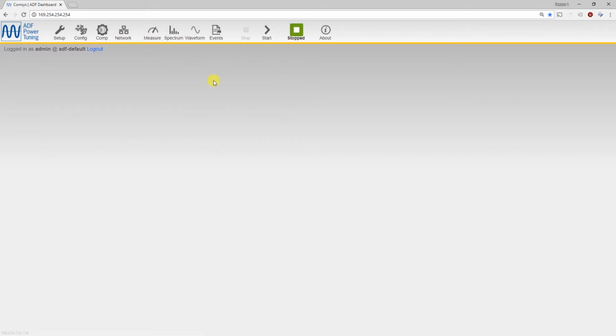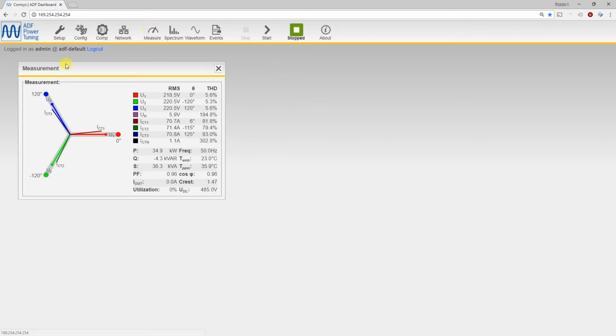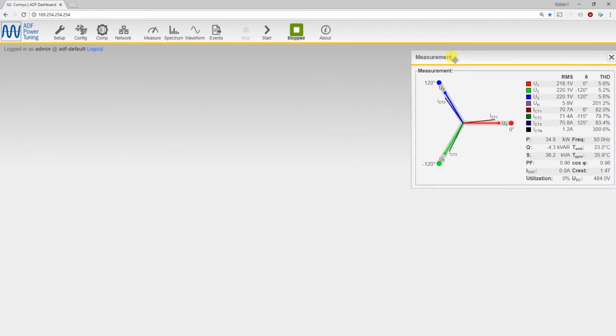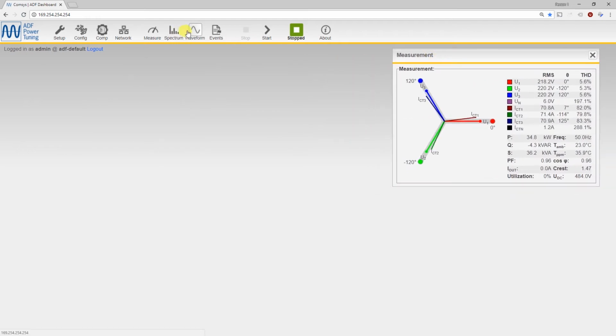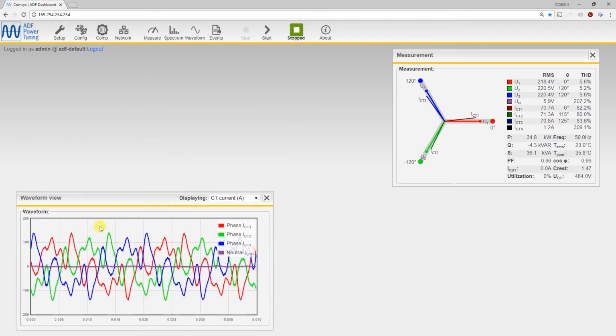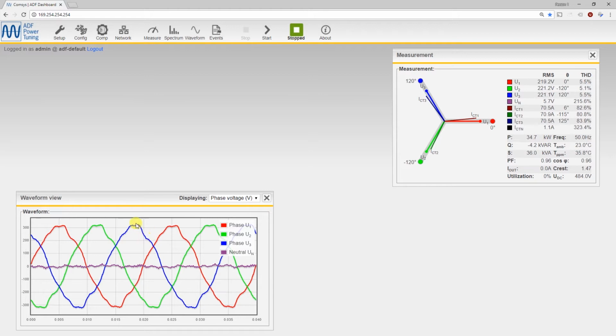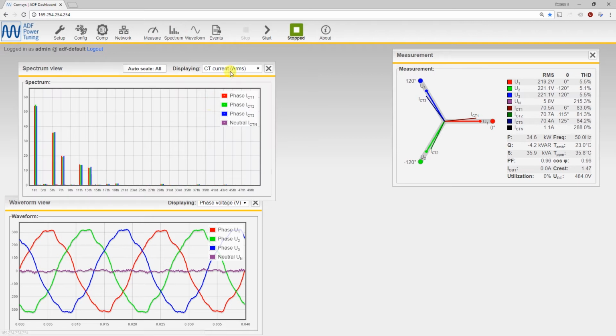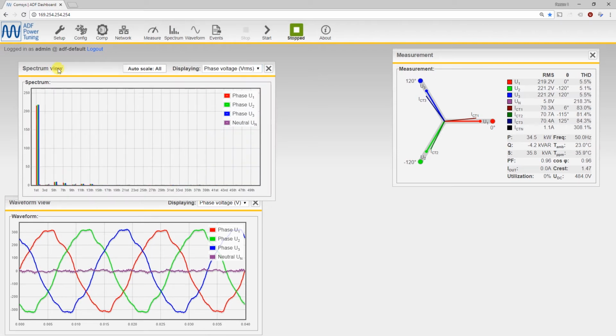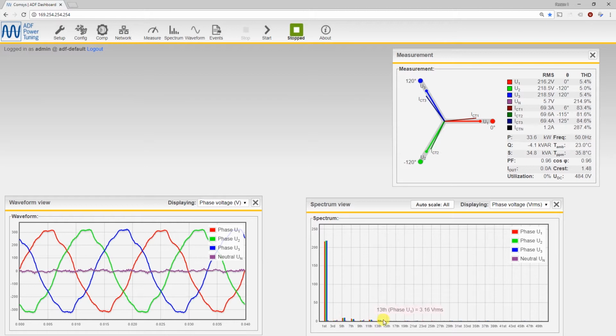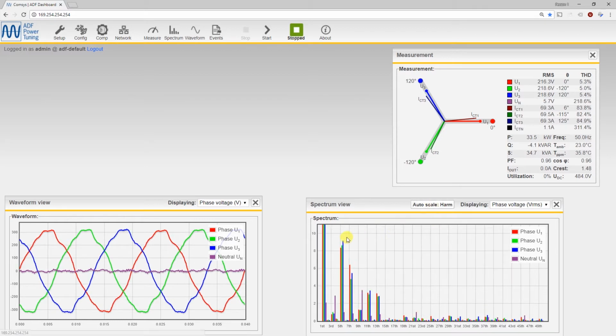To do the sensorless control, we want to open a few windows. An important window always to have open is the measurement window, and then having a waveform open is quite nice. Here we see right now the current distortion. Here we have now the voltage distortion, where we can see there's quite some distorted voltage here. And the spectrum as well, we can have it as voltage distortion. Right now you can't see very much, it's very tiny down here, so we do a scaling to just see the harmonics, and now we can see that we have a large amount of 5th, 7th, and then 11th and 13th harmonic.